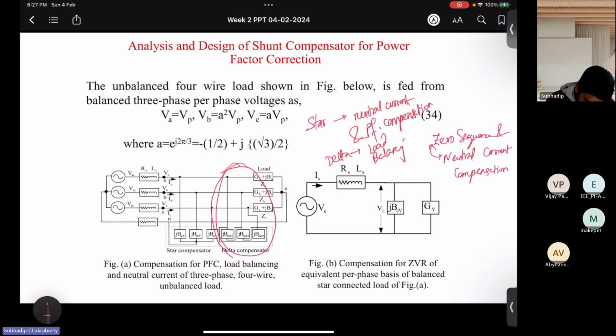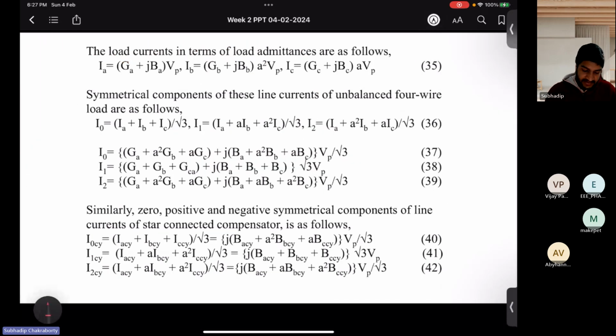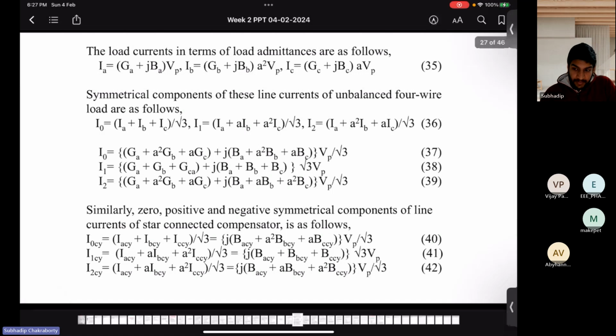So this delta branch, this particular branch, has the role of balancing the load by compensating for the negative sequence currents. Now, since power factor is already taken care of, the loads appear as resistive loads to the source. So all these 2 sets of compensators, these 6 sets, 1, 2, 3, 4, 5, 6, provide the features of neutral current compensation, power factor compensation, and load balancing. And in addition, if someone wants ZVR, then the power factor will not be unity. You already know. Then for ZVR, you just apply the same formula and get the ZVR values per phase.